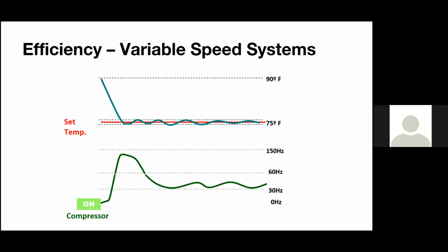So why does this really matter? This matters when you are designing an HVAC system and sizing it. Typically you're going to be sizing it for the worst case scenario, right? So when you size a conventional system for worst case scenario, you're looking at, okay, wintertime, it might be 0 to 5 degrees in the Boston area. And then in the summertime, you might have a glass building or a glass section to your home.